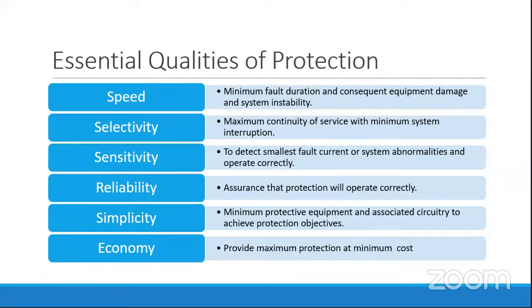Sensitivity is to detect even the smallest fault current or system abnormalities, and to operate the correct switch gears. Reliability is to assure correct operation. If we have a triple line fault, meaning a short circuit condition, then the switch gear should operate for the short circuit condition only, not for any other protection. Simplicity means minimum protective equipment and associated circuitry to achieve the protection objectives. Economy means providing maximum protection at minimum cost.